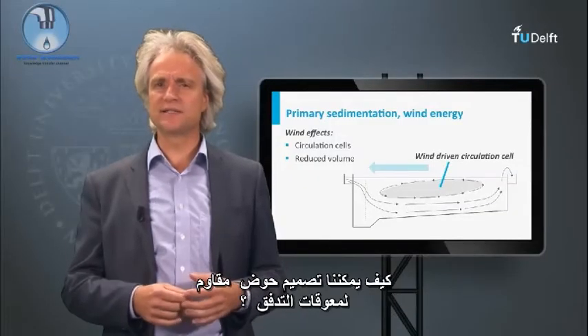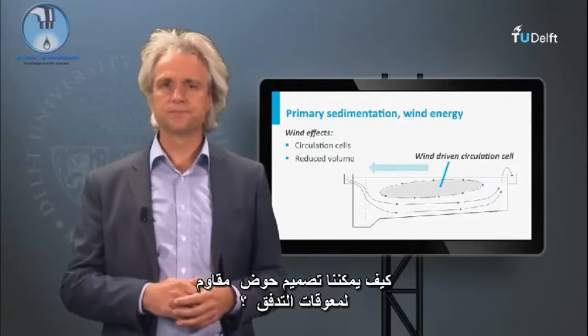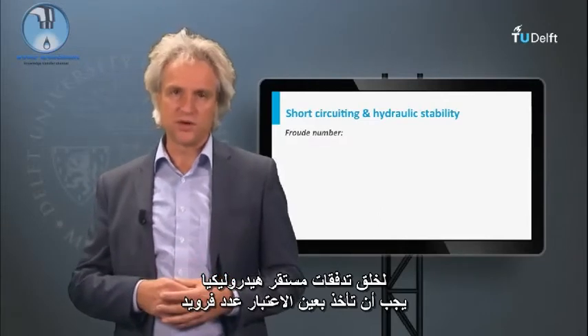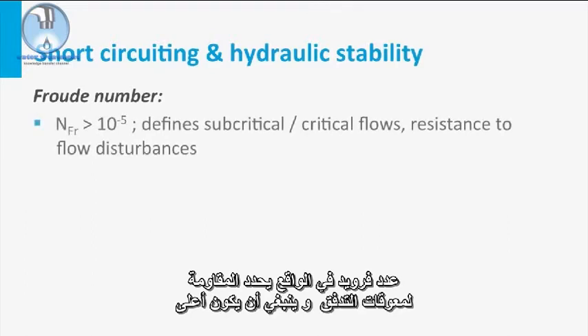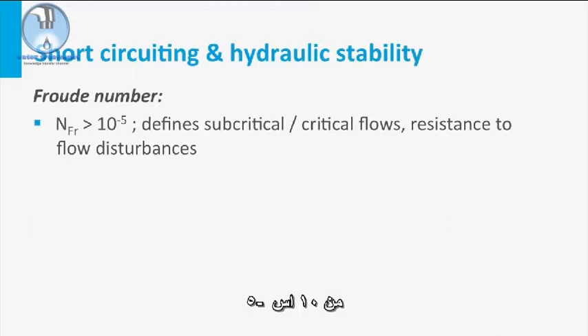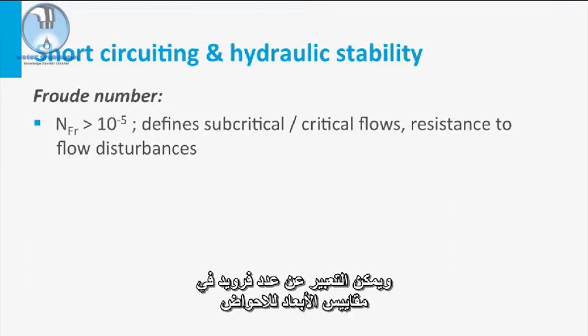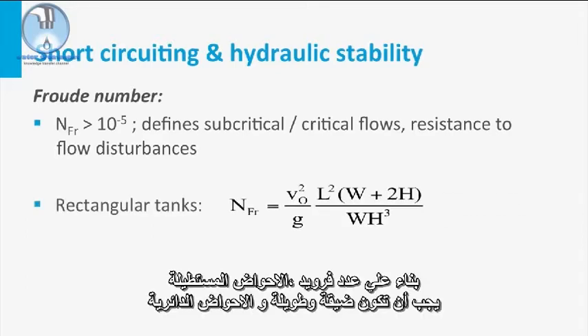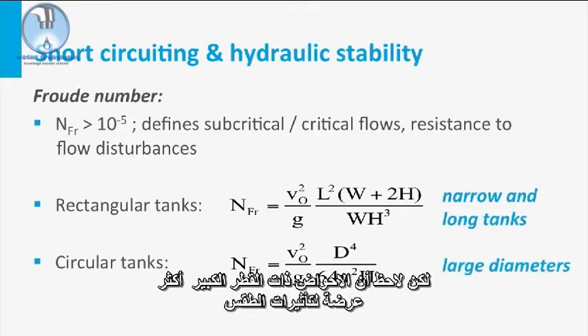How can we design a tank that is resistant to flow disturbances? For creating hydraulically stable flows, we have to take the Froude number into consideration. The Froude number defines the resistance to flow disturbances and should be higher than 10 to the power of minus 5. The Froude number can be expressed in the dimensional measures of either a rectangular tank or a circular tank. Based on the required Froude number, rectangular tanks should be narrow and long, and circular tanks should have a large diameter. Note that large diameter tanks are more susceptible to weather influences.